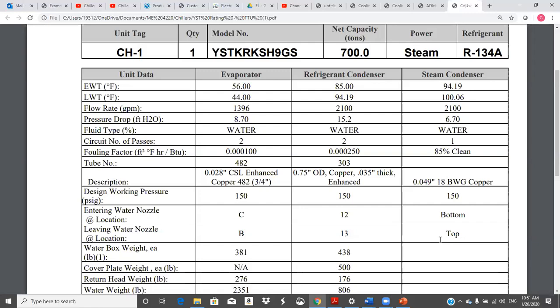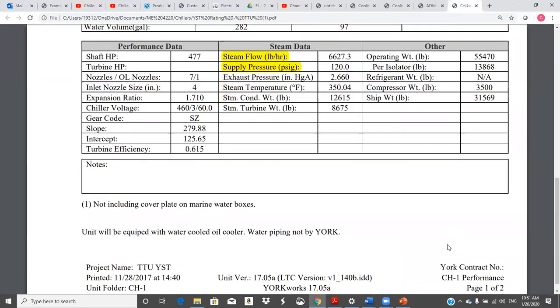Let's look at just, oh, hang on, you got a minute. Here we go. Steam flow, 6627 pounds an hour. Supply pressure, 120. That's what it takes to drive that thing. Now, will that save you money versus a centrifugal? Well, you got to go through the numbers. It depends on the demand. It depends on the electric cost. It depends. You can't just look at these things. If you've done 100 of them, you can probably look at them. But if you've done none of them or one of them or two, you should go back through the numbers.